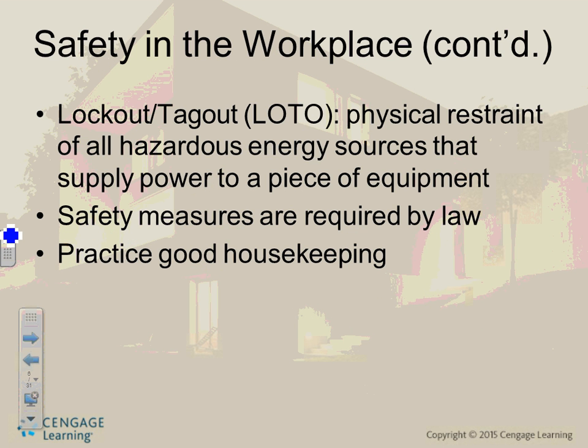So we always start with safety, guys. Rule number one for safety is the so-called lockout, tagout procedures. Basically, OSHA requires that you cannot work on electrical equipment energized, period. If you want to change this ballast, the first thing you need to do is turn it off, lock the circuit breaker that feeds it, tag it, and go change that ballast. Typically, ballasts and circuits are not as much of a concern, but mechanical equipment and all this stuff require lockout, tagout procedure. Any piece of equipment you work on, you go turn it off. Not only turn it off, you lock it and put a tag on it, so nobody other than you can open the circuit, and you can go work on it de-energized.